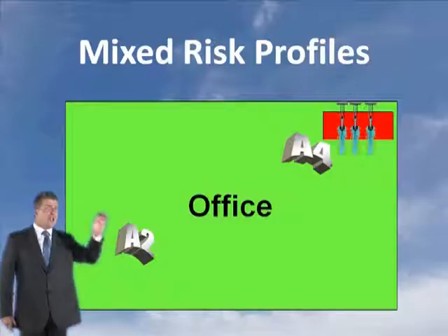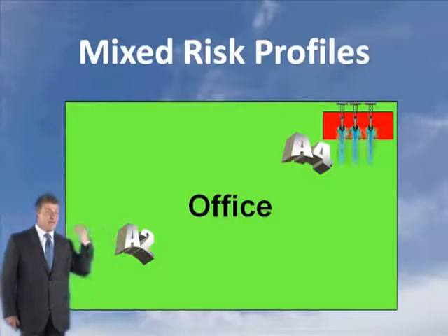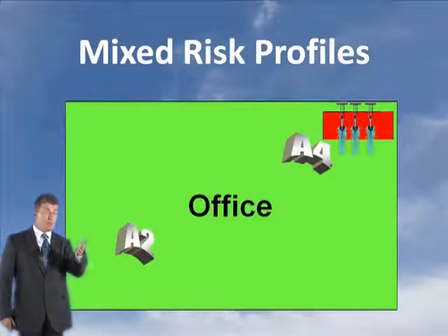Now, you're not allowed an A4. The code won't allow that. So what do you have to do? Well, you have to put some fixed suppression in. So he says, all right, I want my chips. I'm going to put in an Ansul fixed installation in that deep fat fryer. If it catches fire, it'll put it out to the appropriate British standard.